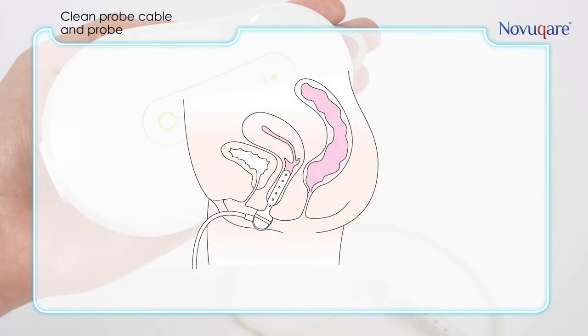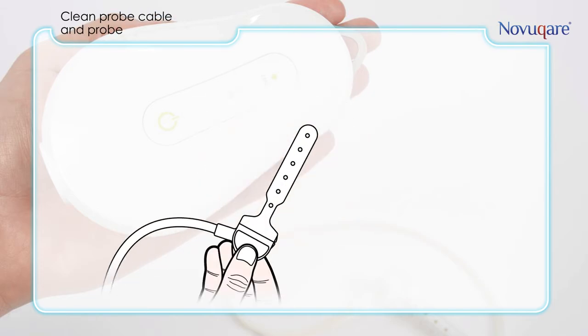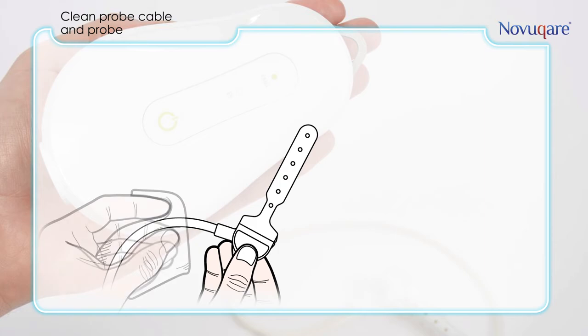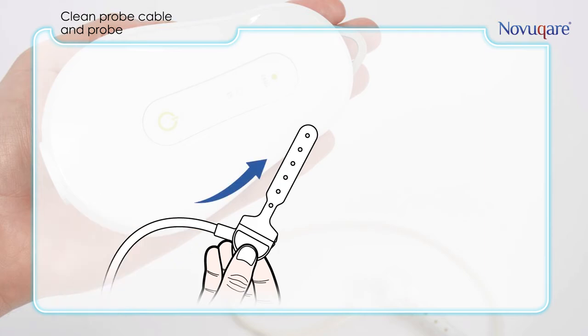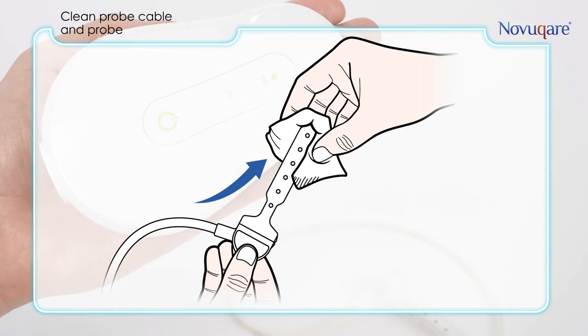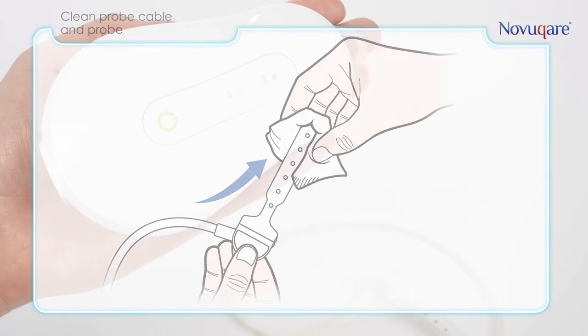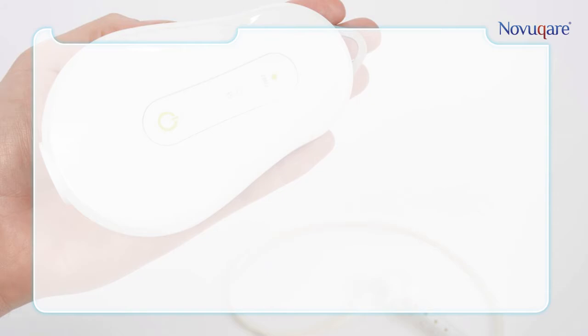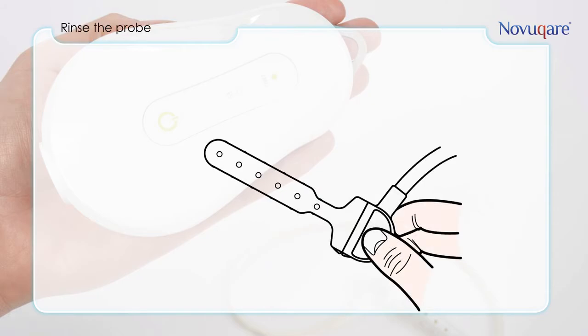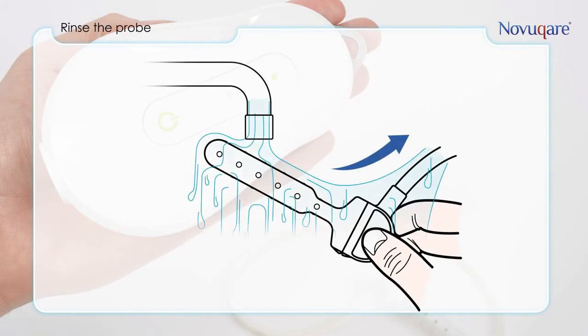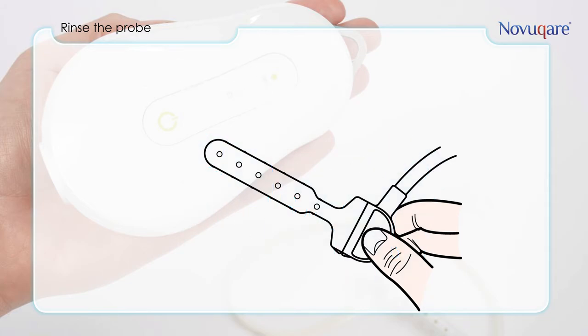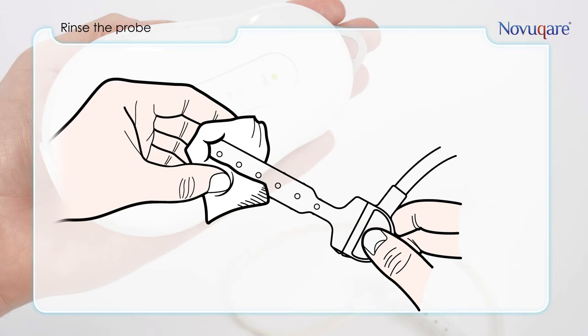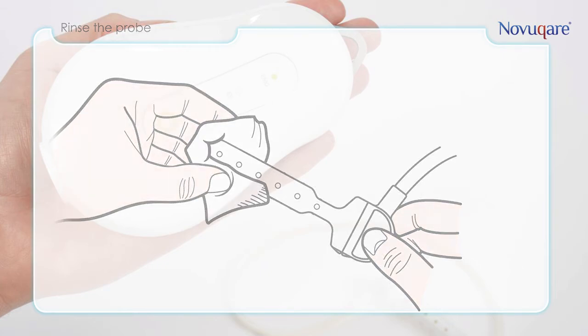Remove the probe from the patient with a gloved hand, but leave it on the probe cable and hold the probe and cable at the connector with your gloved hand. Wipe off cable and probe with a clean tissue with your ungloved hand and throw this tissue away. Rinse the probe, still attached to the cable, under lukewarm water and rinse off probe and first 20 centimeters of the cable while holding it with your gloved hand. Dry probe and cable with a clean tissue and throw this tissue away.